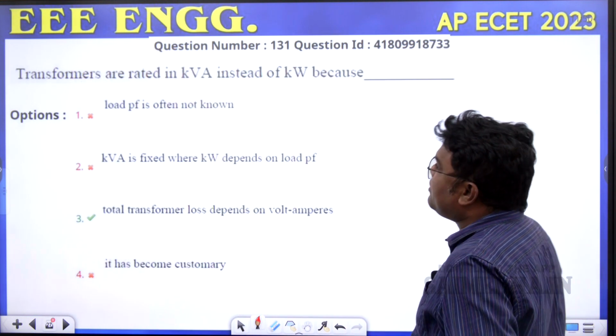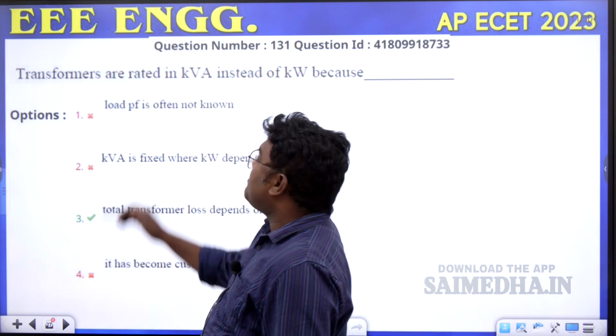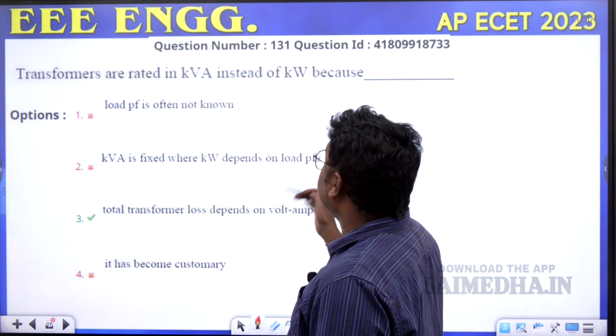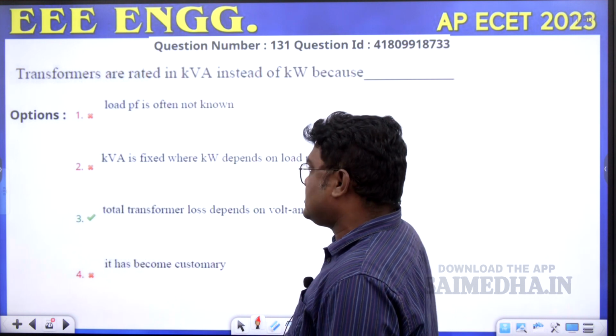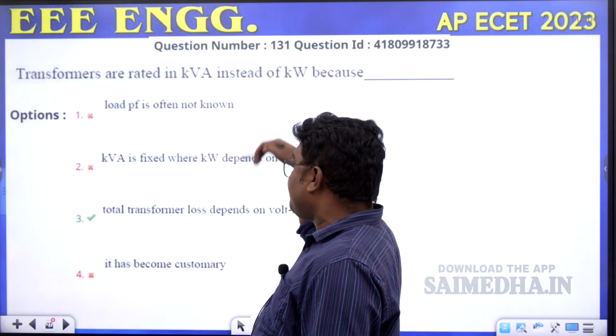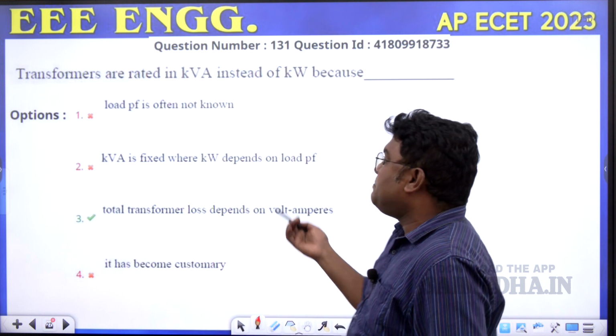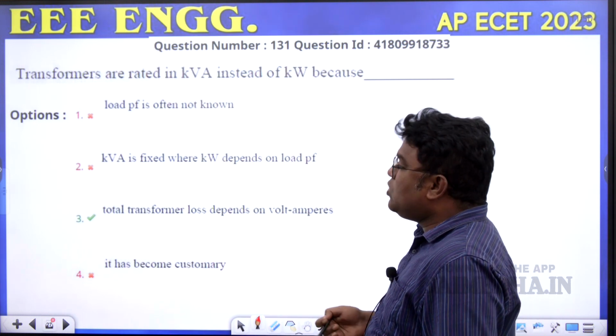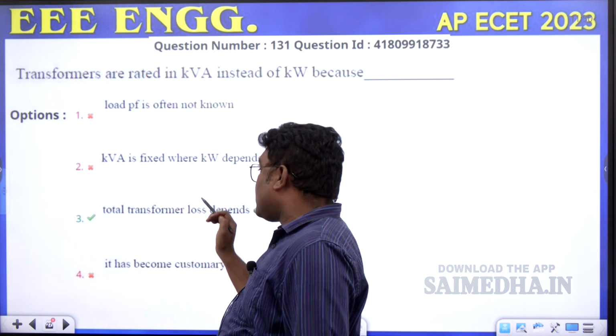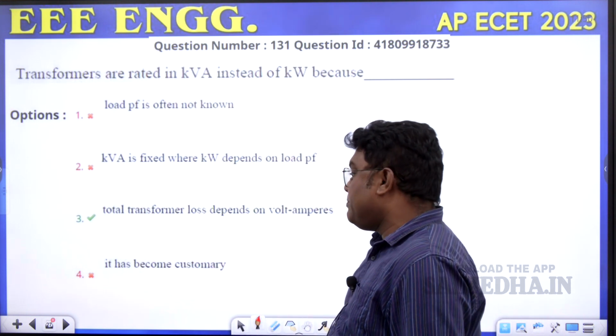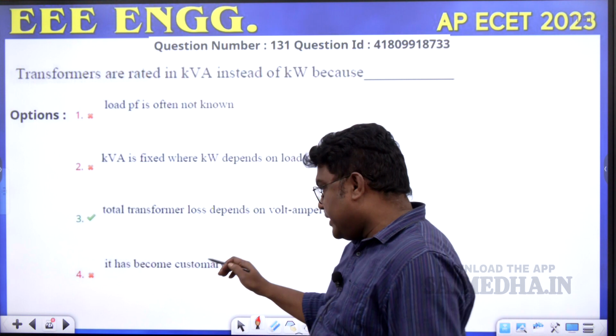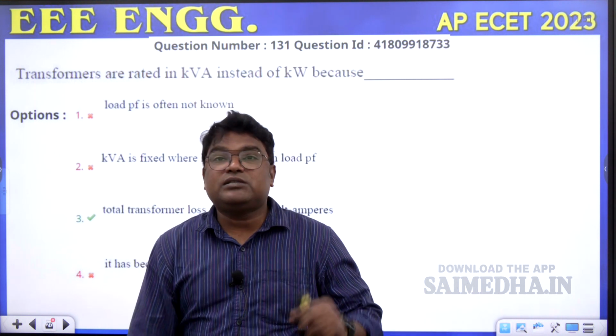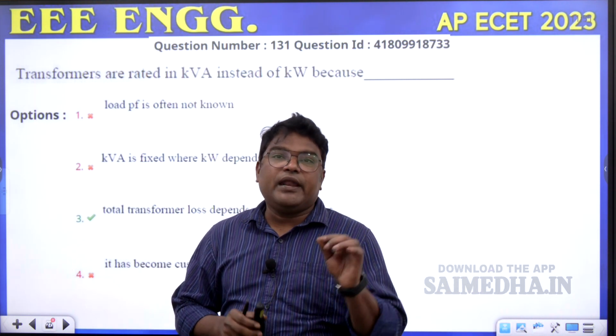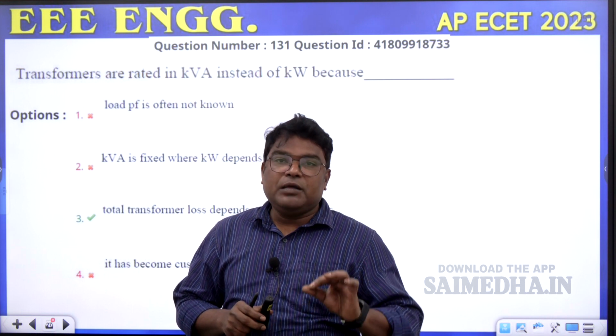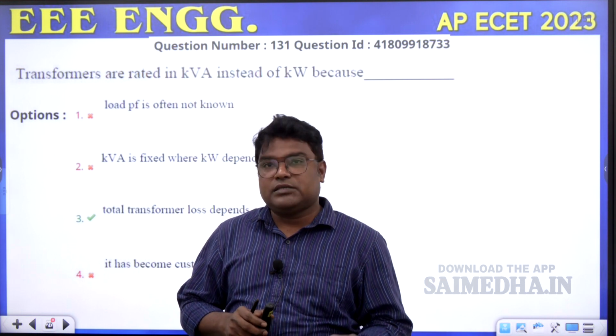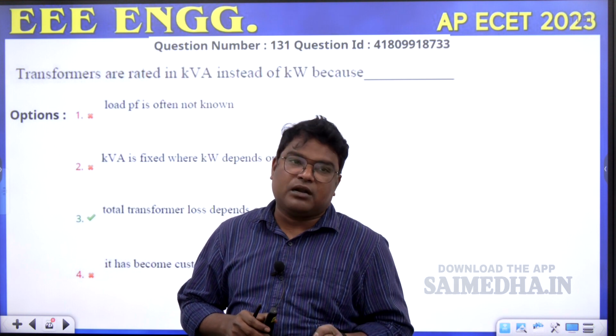And next, question number 131. Transformers are rated in kVA instead of kilowatts because the load power factor is often not known. The kVA is fixed, whereas kW depends on the load power factor. The total transformer loss depends on the volt-ampere. The kVA rating of the transformer depends on the temperature rise, that means the losses of the transformer.